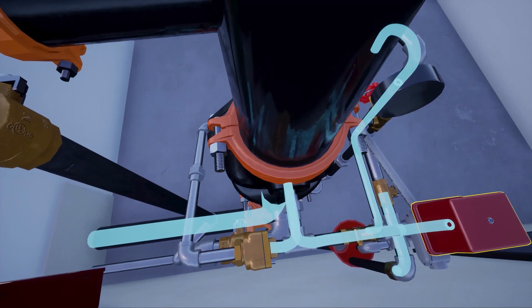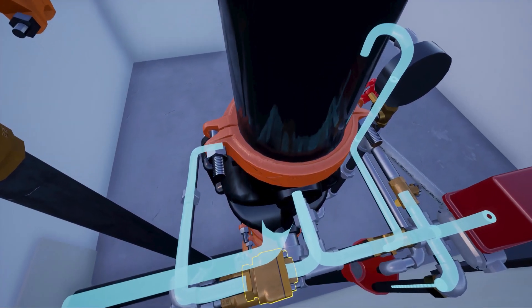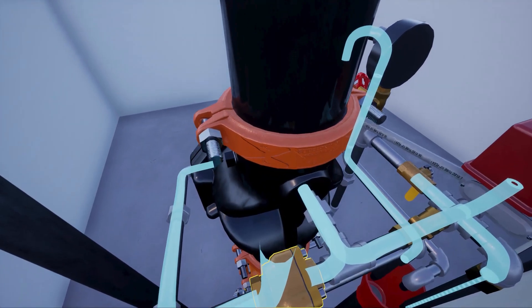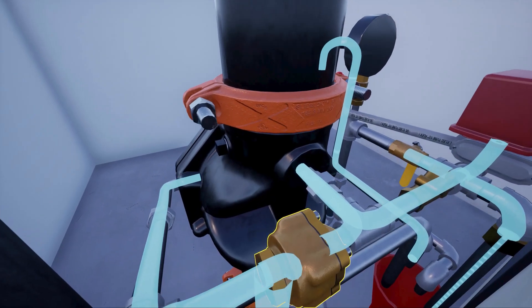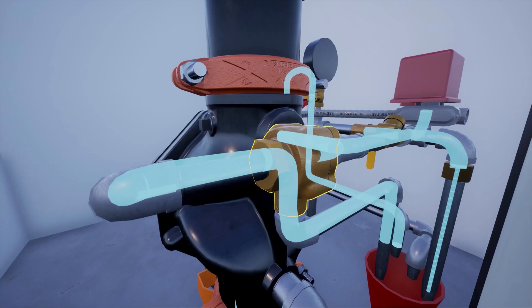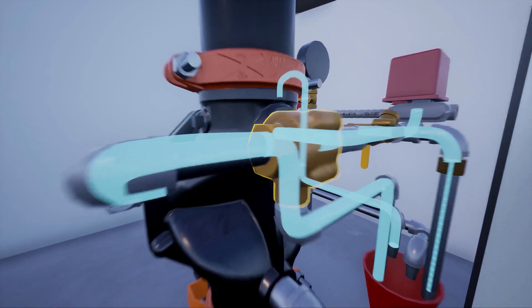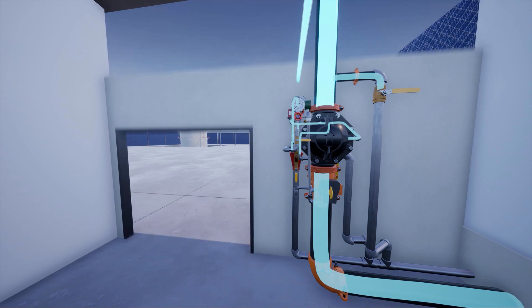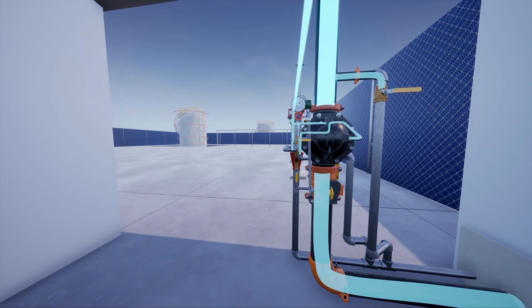Water flows through the outlet chamber of the deluge valve, forcing the push rod of the pressure operated relief valve open, redirecting prime water out to the drain cup. Water flow continues through the deluge system piping to the discharge devices, and the fire is controlled.